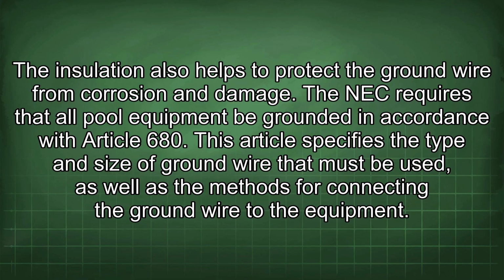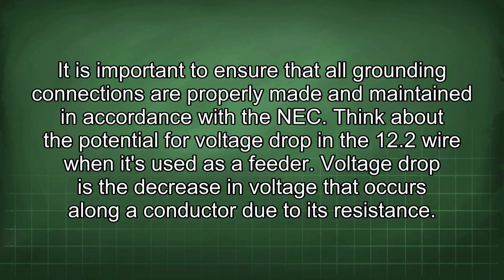The NEC requires that all pool equipment be grounded in accordance with Article 680. This article specifies the type and size of ground wire that must be used, as well as the methods for connecting the ground wire to the equipment. It is important to ensure that all grounding connections are properly made and maintained in accordance with the NEC.